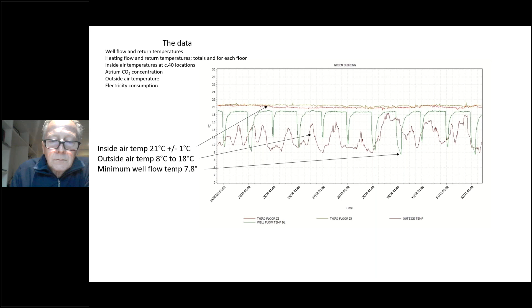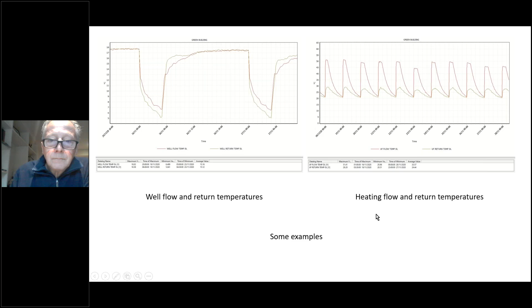That's a little more detail. You can see the heat pump starting off here at midnight, and it gradually pulls the temperature of the water in the borehole down to around 5 degrees. The delta T is what we're extracting from that water. It starts, as I say, at midnight, and it switches off whenever the building reaches its set point, and that happens every night. This is a shot of 11 days, and you can see, again, very consistent, very steady performance.